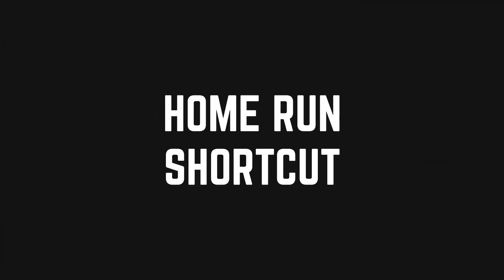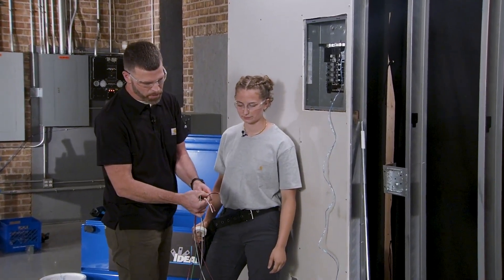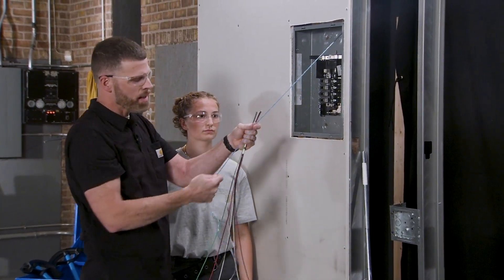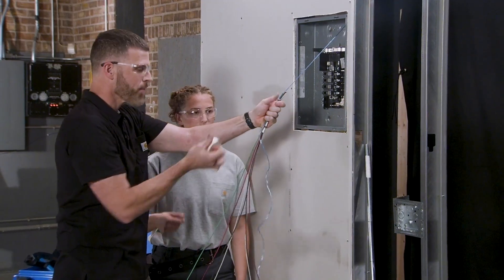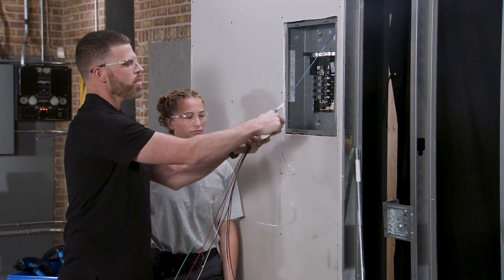It looks like we're going to be running some wire. What do you got for us? We're pulling a home run, and we're going to show you a shortcut of half-hitching the wires on instead of stripping them all to make a head. We got two networks we're pulling — they're already identified with one wrap of tape and two wraps of tape — seven conductors total. If we were to strip them all, we'd get a large head. Something I like to do instead is when I'm using polyline, or if there was a fish tape in this home run, I would just tie a small chunk of polyline to it so I can half-hitch on it and make a wrap.